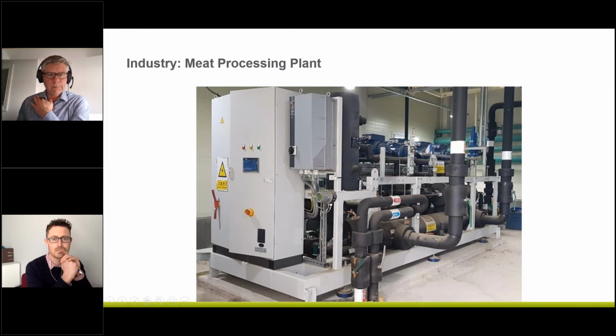So just to wrap up, Michal, the final one is more of a comment than a question. Someone mentions 120 bar would be similar to traditional hydraulic applications, so there's obviously a lot of skill sets in place around hydraulics. I presume that's the gist of it. Yeah, and again, remember the pressure stays inside the skid. It's localized on the heat pump skid. It's not as if the pressure goes out to the system. And you know, the flange connections, you just tie up to both the hot and the cold side.